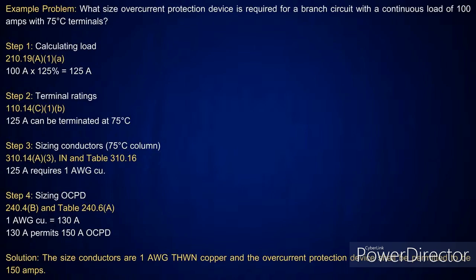Okay. Now, watch as I go down to step 4. How am I going to size the overcurrent protection device here? Well, I can do two options here. If I look in Table 240.6(A), do I have a 125 amp standard overcurrent device listed there? Okay. You could be looking at protecting the load, or I can protect what? The conductor. So what you want to do is go look at 240.4(B), and you'll have in parentheses there, it says it can protect the conductor. In this case, I'm going to protect the conductor, and I have a 130 amp conductor. So the next size above that from Table 240.6(A) is a 150 amp overcurrent protection device.